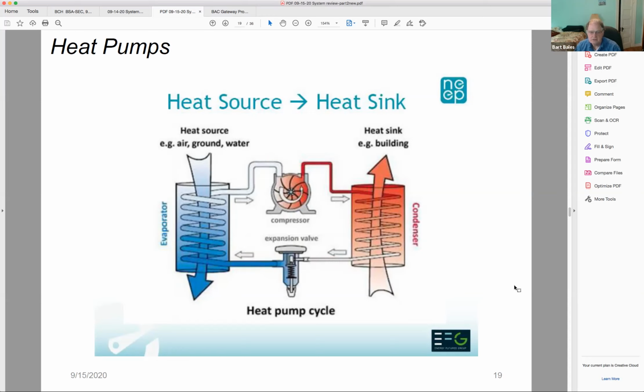In heating, energy is drawn from the ground or the water. That's the blue on the left. And then the fluid moves toward the compressor. The compressor increases the pressure, that increases the temperature and it adds some energy to the fluid as well. And now it's hot enough that heat can transfer from the condenser to the space, and then it goes back through the valve, and the cycle just repeats.